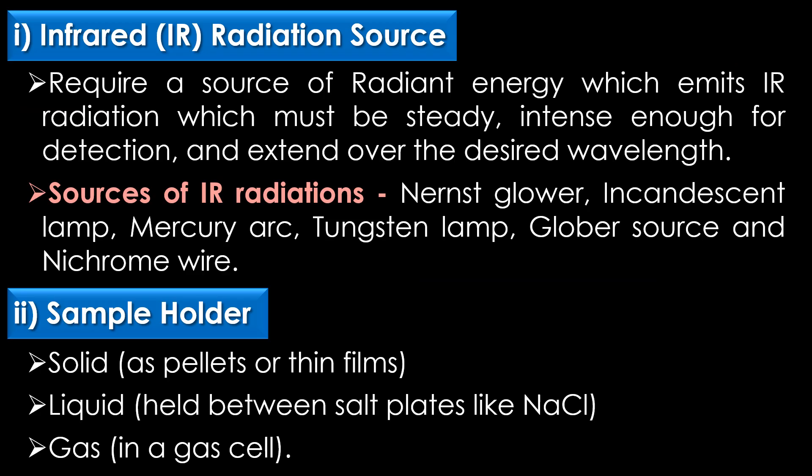The first part is the infrared radiation source. Infrared instruments require a source of radiant energy which emits infrared radiation that must be steady, intense enough for detection, and extend over the desired wavelength. Various sources of IR radiation include the Nernst glower, incandescent lamp, mercury arc, tungsten lamp, globar source, and Nichrome wire.